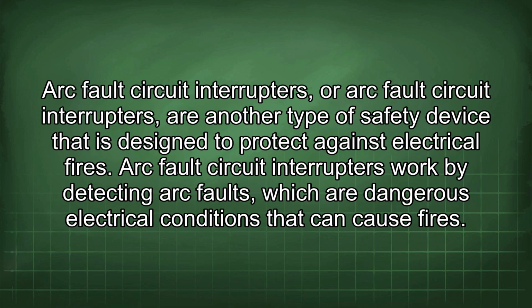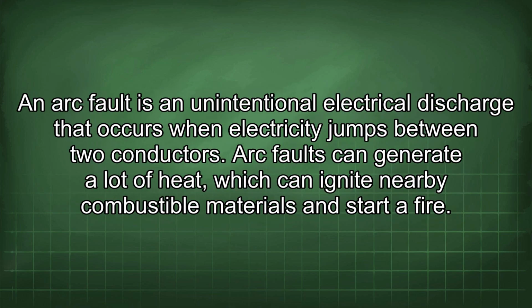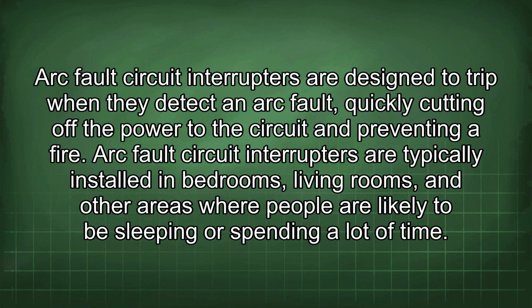Arc fault circuit interrupters, or AFCIs, are another type of safety device that is designed to protect against electrical fires. Arc fault circuit interrupters work by detecting arc faults, which are dangerous electrical conditions that can cause fires. An arc fault is an unintentional electrical discharge that occurs when electricity jumps between two conductors. Arc faults can generate a lot of heat, which can ignite nearby combustible materials and start a fire. Arc fault circuit interrupters are designed to trip when they detect an arc fault, quickly cutting off the power to the circuit and preventing a fire.